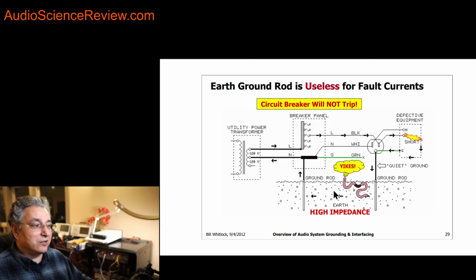For this reason, the National Electric Code, NEC in US, does not allow you to have more than one ground for a premise. From here on, from this line on, you better have a single ground, and this is your ground. You cannot do this. This is against the code, against safety, and there's no reason to do it. It doesn't do anything for noise anywhere. Remember, if there's noise in here and you connect it in here, what's it going to do?